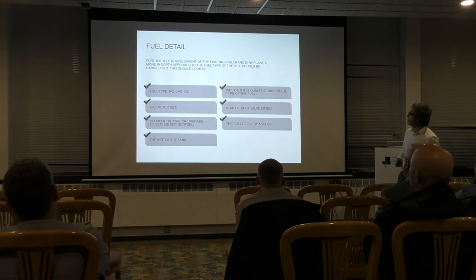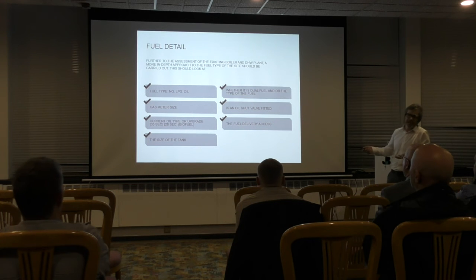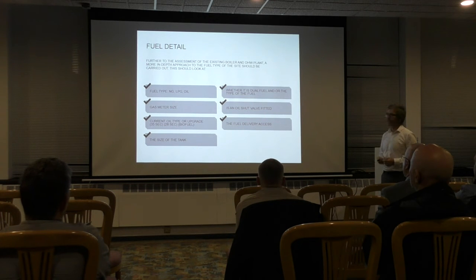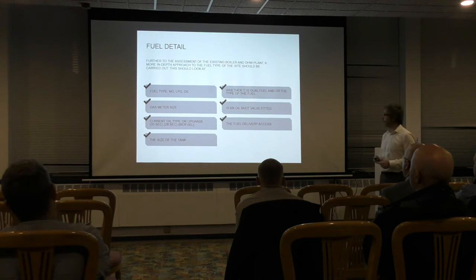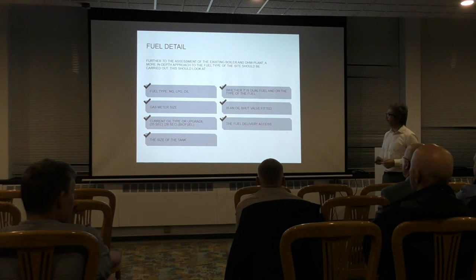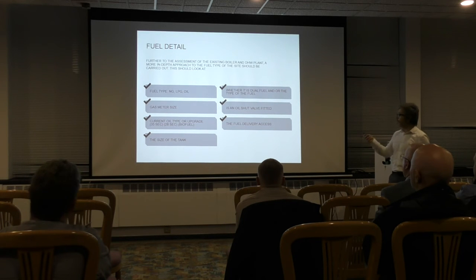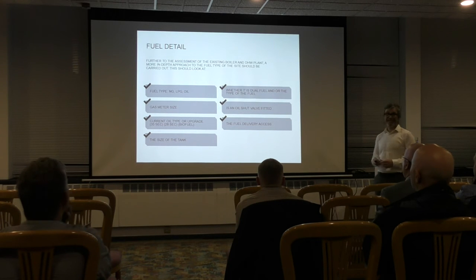And then going on to the fuel again, we're looking at the fuel detail itself. Once we've ascertained whether we're looking at LPG, natural gas, oil, or whatever, if we're looking at gas, for example, we need to be aware of what the gas meter size is. If we're looking at oil, be aware of what oil the boiler is running on. So is it 35 second, 28 second, biofuel? If we are running on oil, what's the size of the tank?